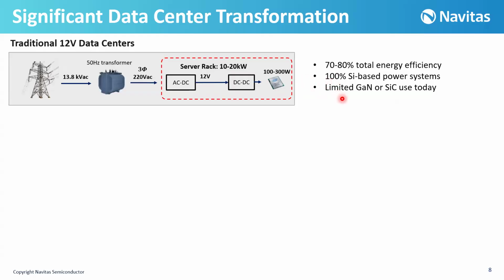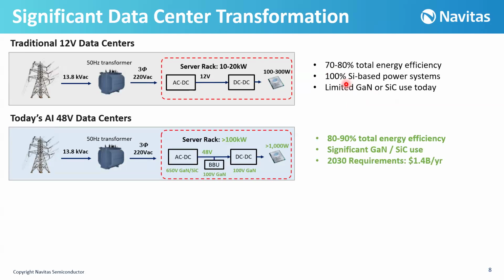Even with the limited gallium nitride or silicon carbide usage we have today, we have low efficiency. Now let's look at today's AI 48-volt data centers. The first stage is the same as the traditional one—we step down to 220 volt AC. But here in the server rack, we step down this voltage to 48 volts. Compared to 12 volts, increasing the voltage to 48 means we are reducing the current flow, which results in lower power loss.